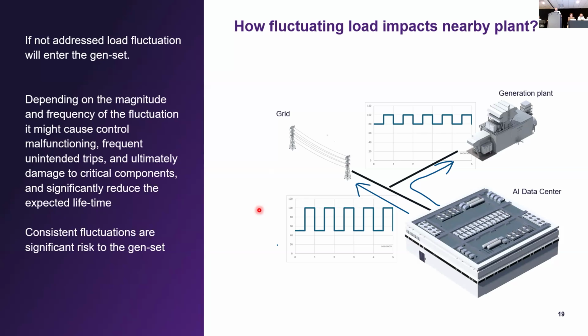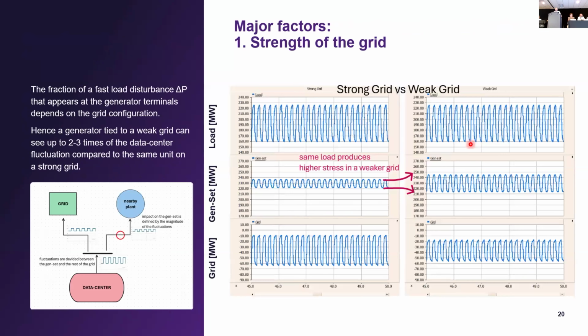So we did some internal investigations. The first question we wanted to answer is, okay, I have the data center connected to the grid, and somewhere nearby I have rotating equipment. We took a large gas turbine nearby. The first question is, how much of this fluctuating load will actually be seen by the generator, and how much will be consumed by the rest of the grid? At which point do we need to start to worry? So we did a very simple study in PSCAD, where the data center is represented by a fluctuating load, where we just vary different frequencies, different amplitude, and different shape.